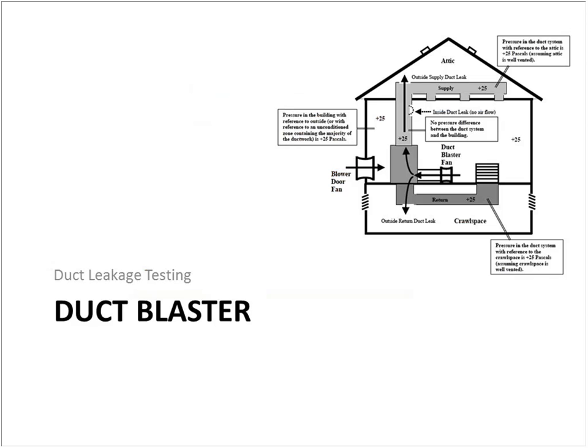Duct blaster testing. This is the device that we use to test for duct leakage to the outdoors. I'll see if I can improve the size of this a little bit. Obviously, any ductwork that's in the attic or in unconditioned crawl spaces is outside of the thermal envelope of the home. And even if it has insulation over it, if it's not full insulation and it doesn't have an air barrier to encapsulate that in an attic, then it's considered outside, and that triggers duct leakage testing.